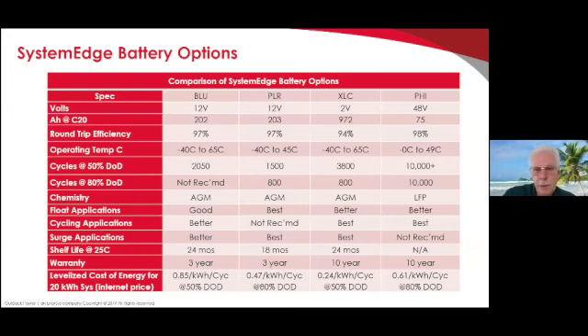But if you're just going to be backing up your home a couple weeks of the year, 800 cycles is more than enough. So that's another way of looking at this. You can see what happens on the XLCs when you discharge down to 80%, you really lose a lot of cycle life. So it's better to keep these at a 50% depth of discharge.